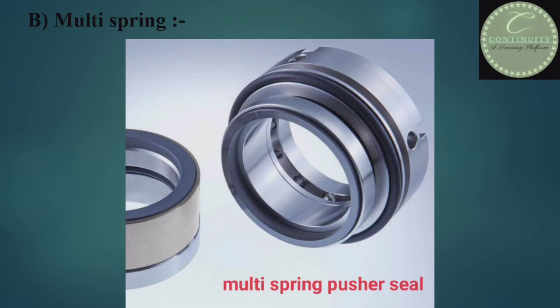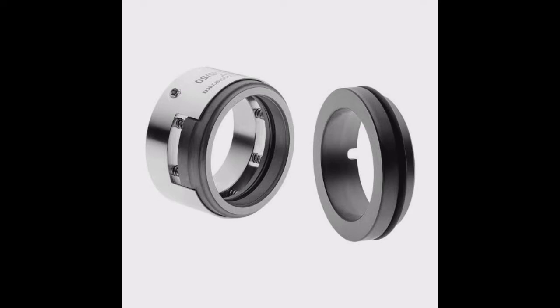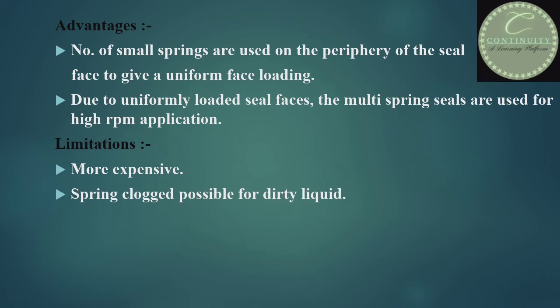Looking at this figure, this is a multi-spring seal — it has multiple springs, not a single spring. Advantages of the multi-spring seal: small springs are distributed on the periphery of the seal face to give uniform face loading, since a single spring does not provide uniform loading on the seal faces. Due to this uniform loading, multi-spring seals are used for high RPM applications. Disadvantages: it is more expensive than the single spring seal, and spring clogging is possible with dirty liquid.